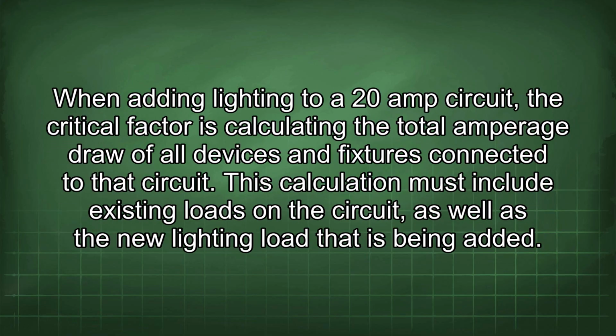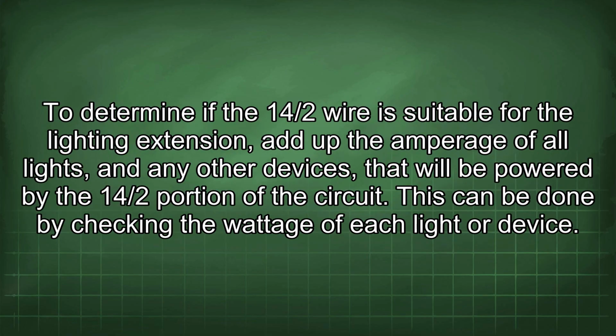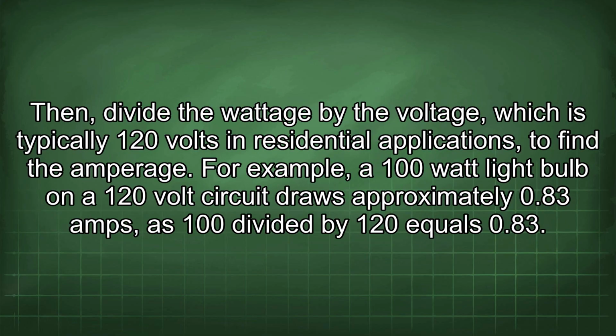When adding lighting to a 20 amp circuit, the critical factor is calculating the total amperage draw of all devices and fixtures connected to that circuit. This calculation must include existing loads in the circuit, as well as the new lighting load that is being added. To determine if the 14/2 wire is suitable for the lighting extension, add up the amperage of all lights and any other devices that will be powered by the 14/2 portion of the circuit. This can be done by checking the wattage of each light or device. Then, divide the wattage by the voltage, which is typically 120 volts in residential applications, to find the amperage.